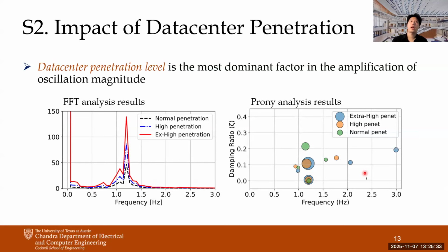And then we increase the data center penetration level from 10% to 20% and 30%, and accordingly, as the data center penetration level increases, there is a larger magnitude of oscillation. You can check it from this left figure, which shows the FFT analysis results. But compared to the previous case, you can see from the Prony analysis results that there's no significant difference in the oscillation frequency and the damping ratio in these penetration level cases. So basically, there's only a difference in the size of the circles. And notably, the data center penetration level was the most dominant factor, compared to the other factors, in the amplification of the oscillation magnitude.